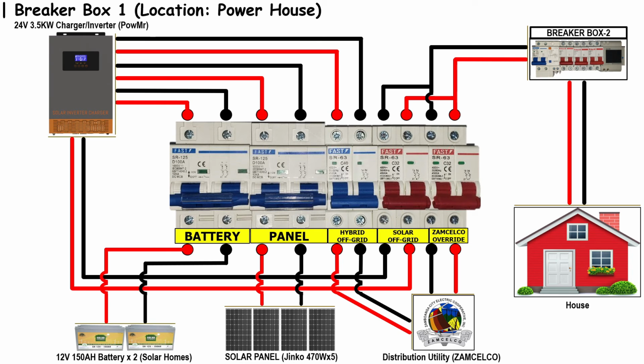By the way, I have two breaker boxes: one located in my Powerhouse and the other inside the main house. This will be my breaker box 1. At number 1, this 100 ampere DC breaker connects my PowMr hybrid inverter to my batteries. At number 2, another 100 ampere DC breaker connects my PowMr hybrid inverter to my solar panels.